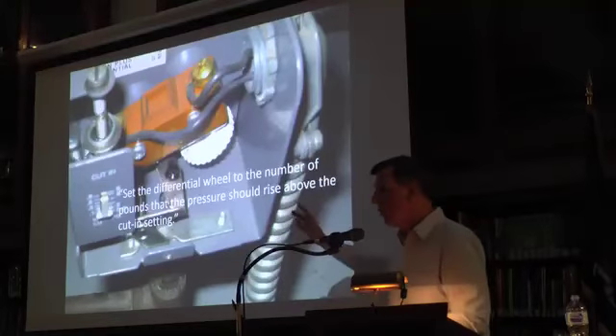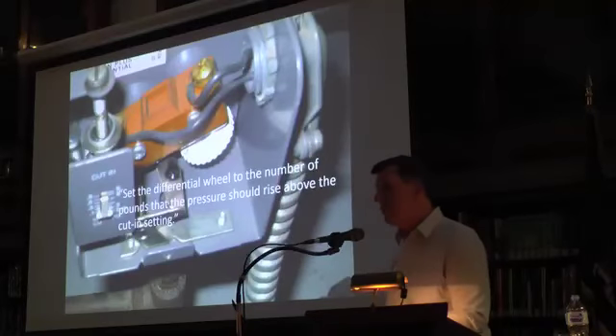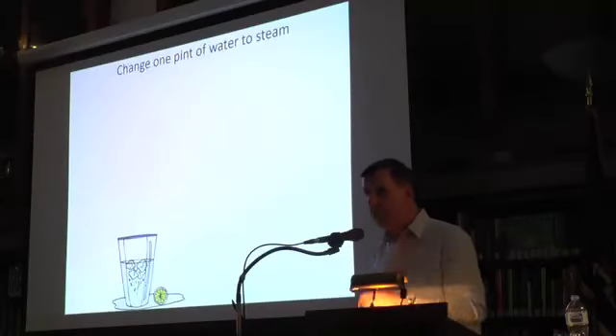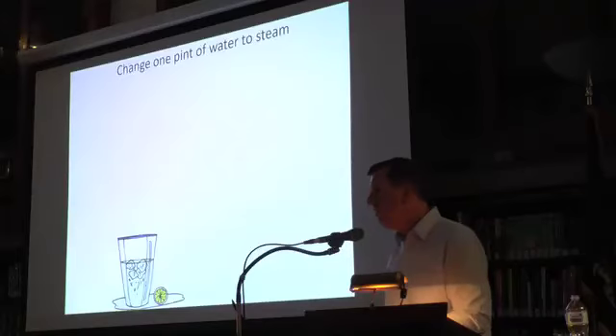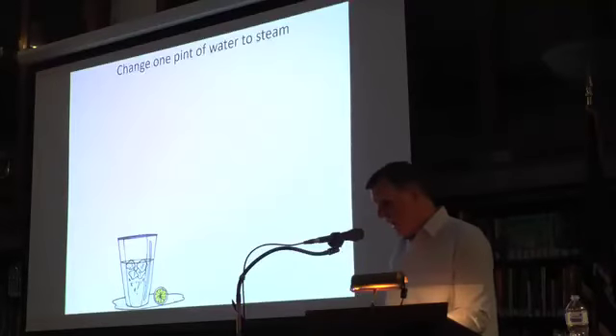So if you started out with 2 pounds of pressure at the boiler, 1,600 feet down the line, or 160 feet up in the air, you're still going to have 1 pound of steam pressure left at the radiator, which is by definition how we describe the term equivalent direct radiation for radiator sizing, EDR. 1 square foot of EDR puts out 240 BTUs when there's 70 degree air on the outside of the radiator and 215 degree steam on the inside, which is 1 pound.